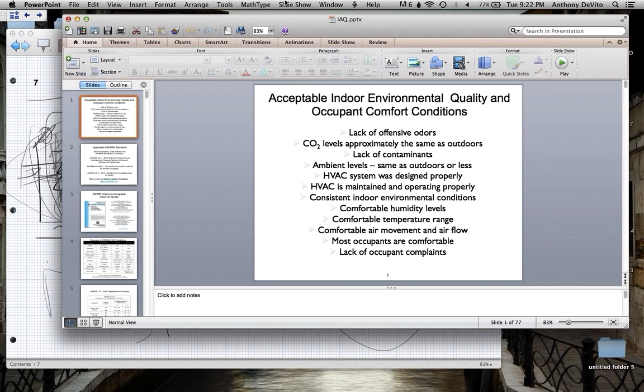That's nonsense, that's not true, right? Because you'll never get them the same as outdoors—you'd have to be outdoors to get them the same as outdoors. You will always have elevated levels of CO2 indoors over what you have outdoors. Because what do you got indoors? You got mammals breathing indoors, a lot of them, so they're contributing CO2. CO2 levels go up. If you completely closed up the building, the oxygen levels would drop, the CO2 levels would go way up, and so on and so forth.